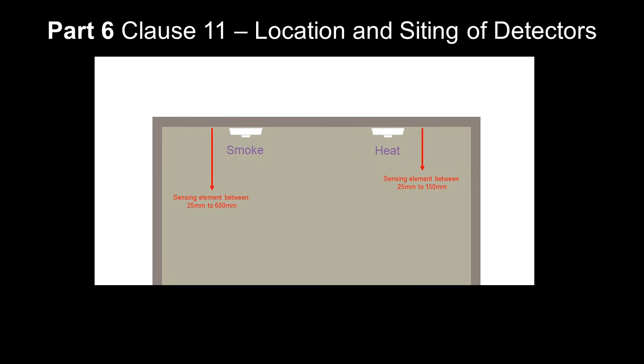So ignore the 25mm, but that's why we don't recess some smoke detectors, because their sensitive elements are below the ceiling as such. So that's why they're quite proud of the ceiling, if you like. But what we're saying is that smoke detectors can go up to 600mm below the ceiling level, and 150mm for heat detectors. So obviously we put them on the ceiling most of the time, but you might have two levels. So just have a think about that, because you can put it on a higher or the lower level.